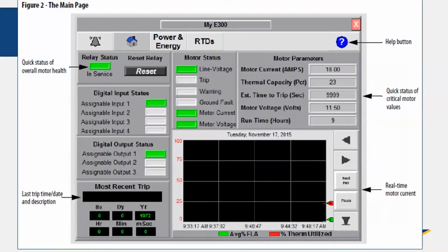So here, this is a screenshot of a faceplate for that E300. So this faceplate is already pre-engineered, pre-designed by Rockwell. And this enables you to pull out all that data that we were talking about here. So you see some clear green lights that kind of tell you the status of the overload, tell you the status of the inputs and outputs. You also have a chart here that kind of trends the full load amps, and then also can trend your percent of thermal capacity. And then on the top right there, you see the actual thermal capacity being displayed. Here it says 23%, so no problems there. But as that continues to climb, we could set alerts up, and then right underneath that, we have the estimated time to trip. So again, just very powerful. The fact that all this engineering is already done for you, you combine this with the add-on profile, and it just helps to make for a quick installation for a pretty high-tech overload.